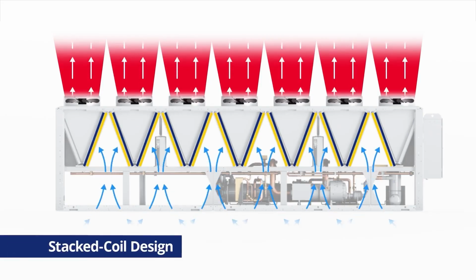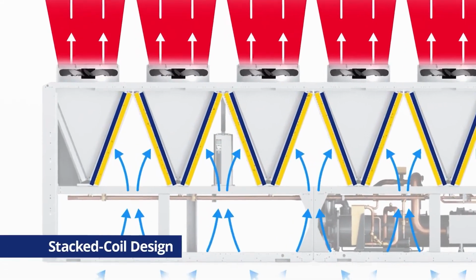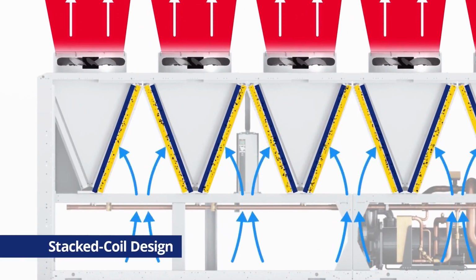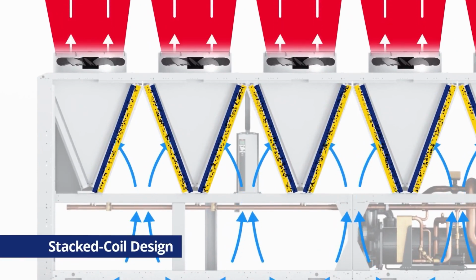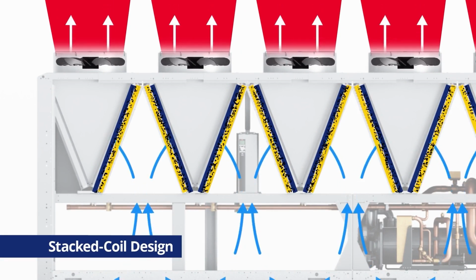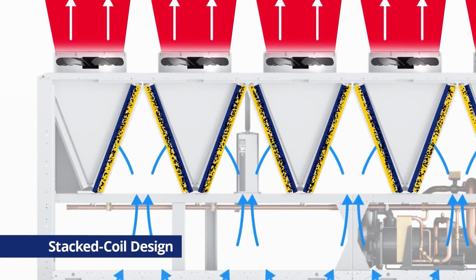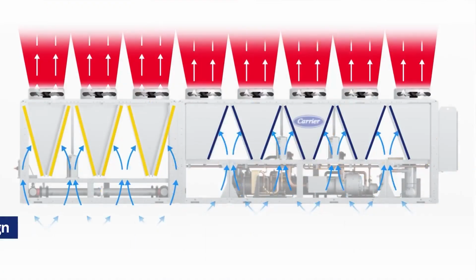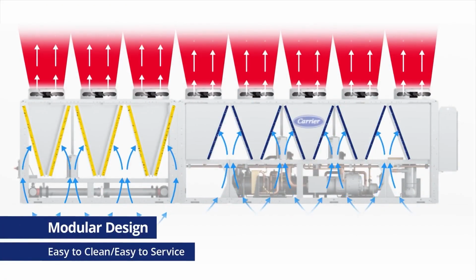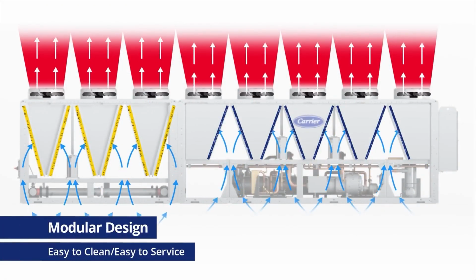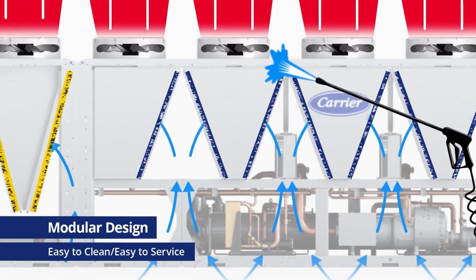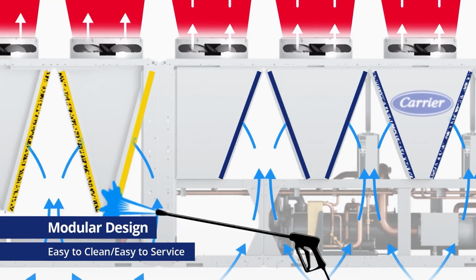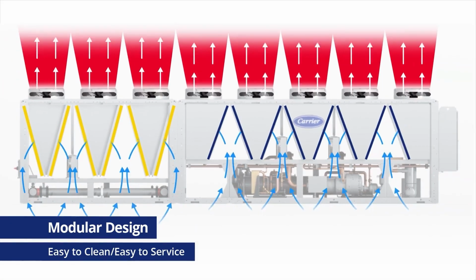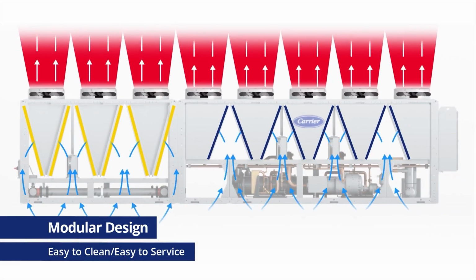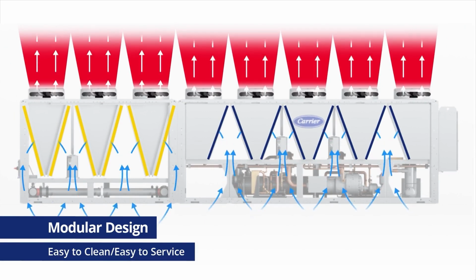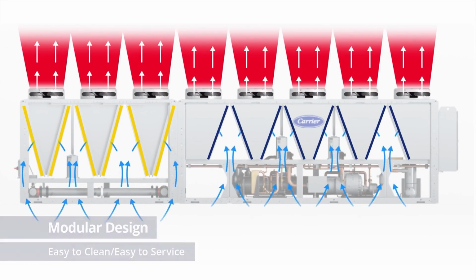With the stacked coil design, as the air flows over two closely coupled coils, one of them essentially becomes a filter, trapping dirt and debris between the coils. This can make cleaning and coil replacement extremely difficult. With the modular design, there's only one coil, so most dirt is expelled by the existing fans. A normal coil wash will eliminate any remaining dirt. In addition, service can be done on either the mechanical or free cooling side of the system, without taking the other side of the system offline.